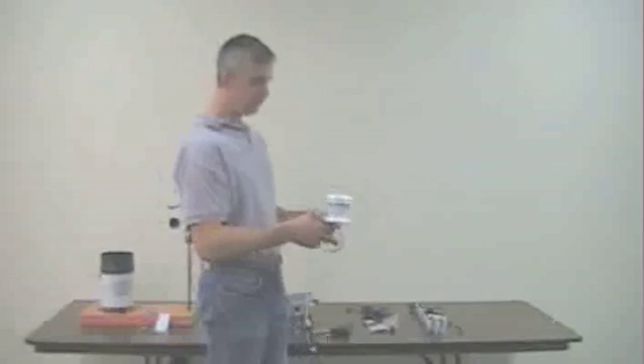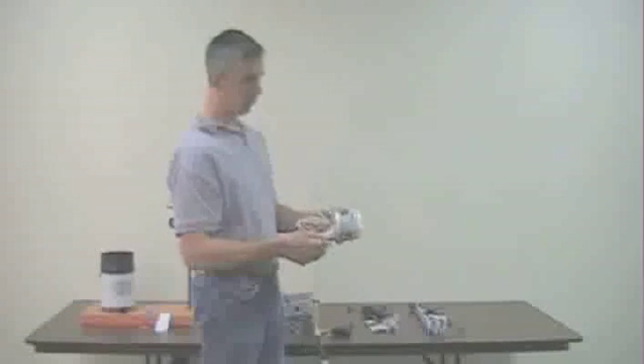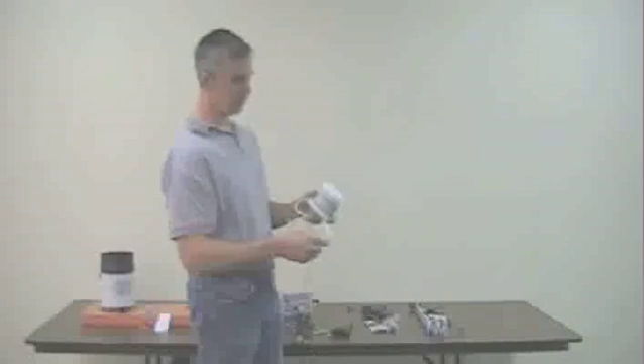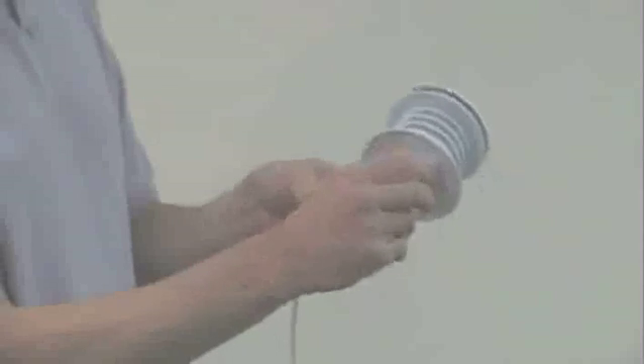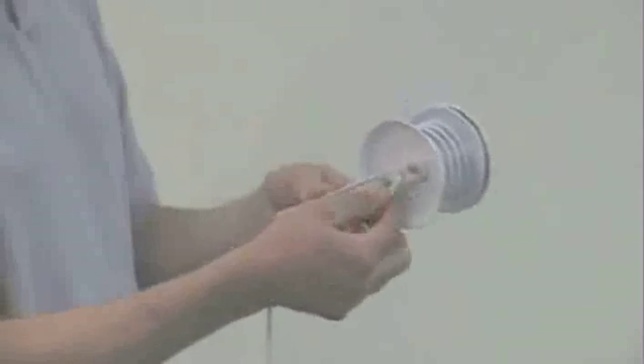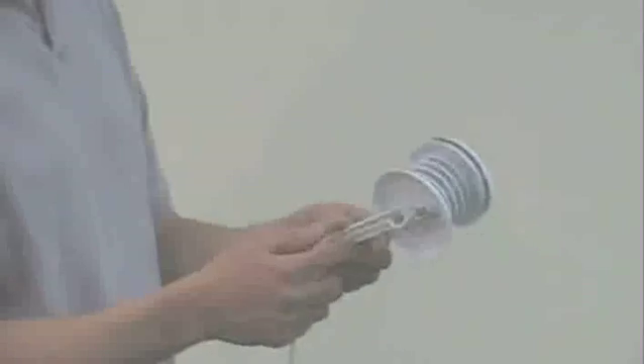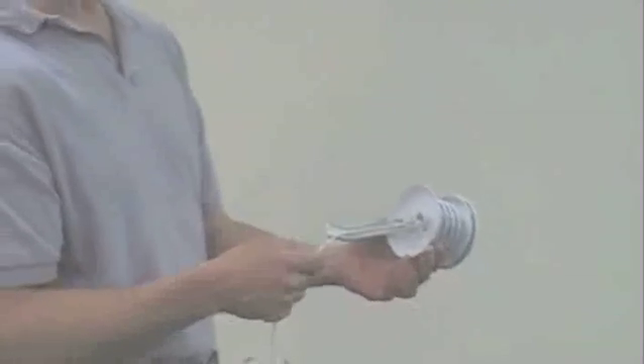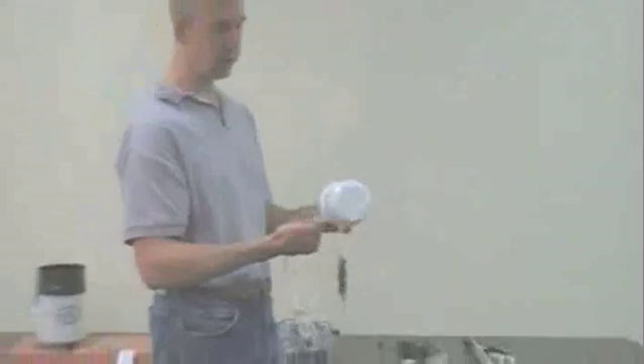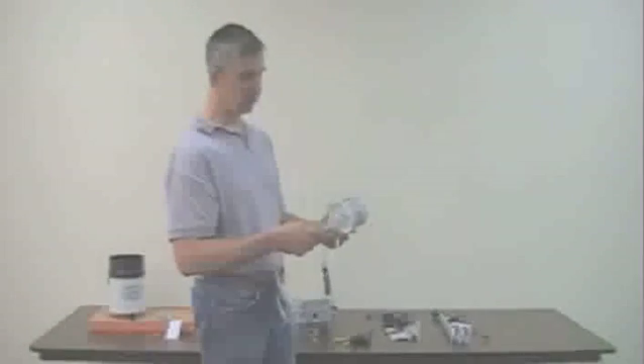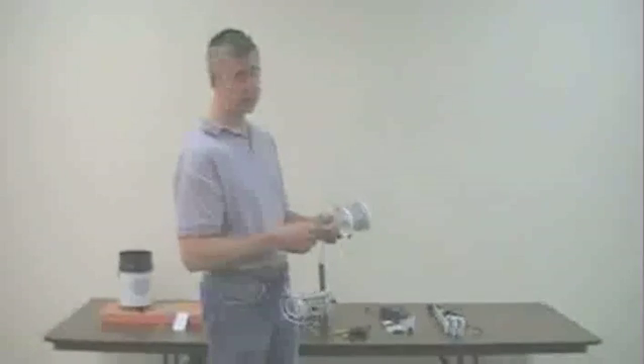And here we have solar radiation shield that has a relative humidity sensor in it that actually records temperature as well. There was a little bit of assembly involved on this unit. You can see the two brass thumb nuts underneath here. And that the cable has been attached to the bracket using a couple of tie wraps. Once again, I advocate doing that in the laboratory. Just the less pieces you have laying around, the less likely you are to lose something.